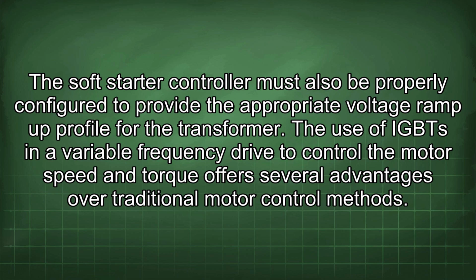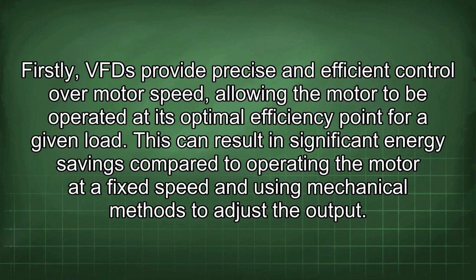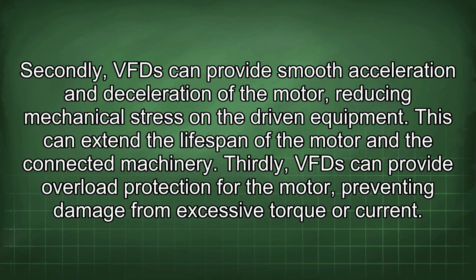The use of IGBT in a variable frequency drive to control the motor speed and torque offers several advantages over traditional motor control methods. Firstly, VFDs provide precise and efficient control over motor speed, allowing the motor to be operated at its optimal efficiency point for a given load. This can result in significant energy savings compared to operating the motor at a fixed speed and using mechanical methods to adjust the output. Secondly, VFDs can provide smooth acceleration and deceleration of the motor, reducing mechanical stress on the driven equipment. This can extend the lifespan of the motor and the connected machinery.